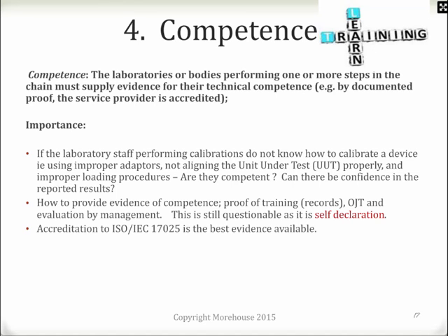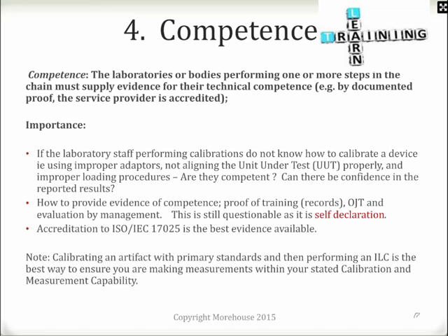How to provide evidence of competence? Well, we can do that by proof of training records, on-the-job training, OJT, and evaluation by management. This is still questionable as it is self-declaration. I can say I'm competent, but how do I prove it? Really, accreditation to ISO/IEC 17025 is the best evidence available. Though, for those listening, I really believe the best evidence to prove competence is by calibrating an artifact with primary standards and then performing an in-house ILC by yourself against that artifact to ensure your measurement uncertainties are what they claim to be.